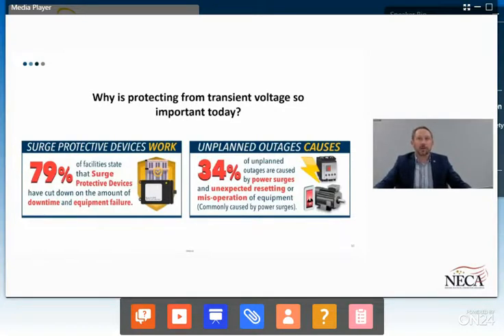Again, it's not just equipment failure, and this is what opens most people's minds up - it's also misoperations. Going to reset a PLC for an unknown reason - well, your operation shut down and you still have downtime. So I think the most important thing I can convey is you can't look at your operation in the traditional sense of electromechanical. You've got to look at it that everything has a computer in it, and it's all sensitive to transient voltage now.